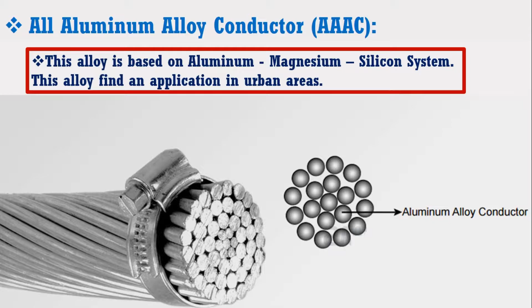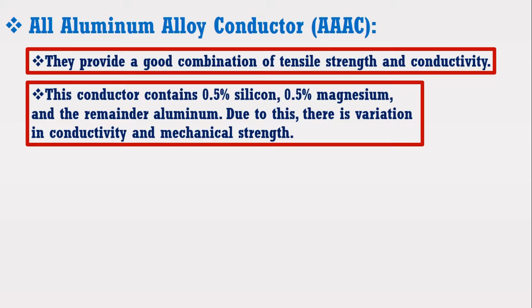This alloy is based on aluminium, magnesium, silicon system as shown in the figure. This alloy finds an application in urban areas. They provide a good combination of tensile strength and conductivity. This conductor contains 0.5% silicon, 0.5% magnesium and the remainder aluminium. Due to this, there is variation in conductivity and mechanical strength.